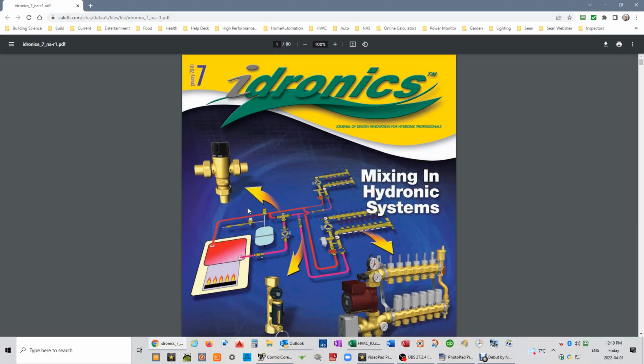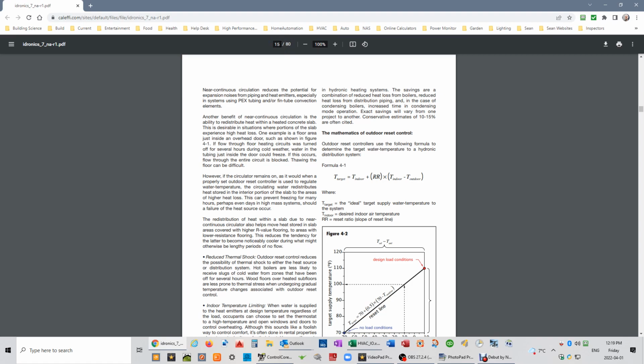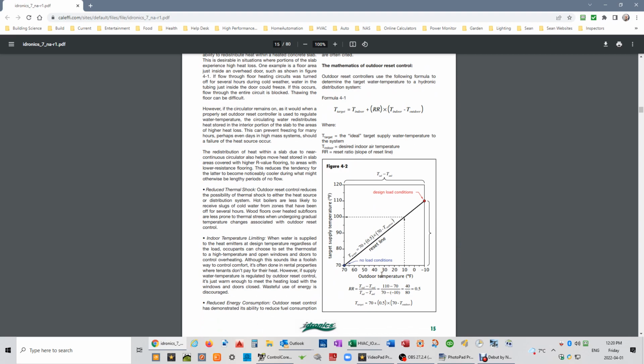So I found that formula in the January 2010 edition of idronics. And on page 15 is a formula that has been written by John Siegenthaler. It basically says your target temperature equals your indoor required temperature plus a reset ratio times your required indoor temperature take away outdoor temperature. So fairly simple. And that reset ratio is based on the overall designed heat loss or heat load of the house at the design set temperature.